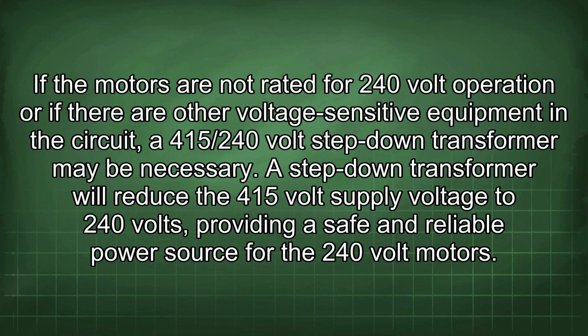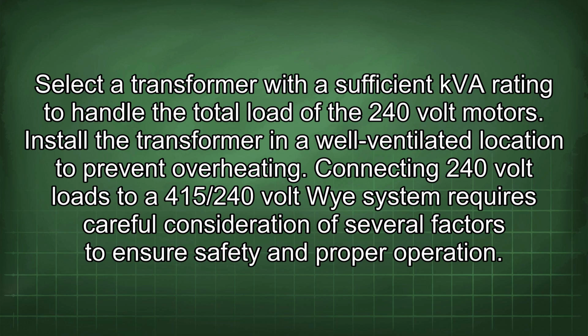If the motors are not rated for 240-volt operation or if there are other voltage-sensitive equipment in the circuit, a 415/240-volt step-down transformer may be necessary. A step-down transformer will reduce the 415-volt supply voltage to 240 volts, providing a safe and reliable power source for the 240-volt motors. Select a transformer with a sufficient kVA rating to handle the total load of the 240-volt motors. Install the transformer in a well-ventilated location to prevent overheating.